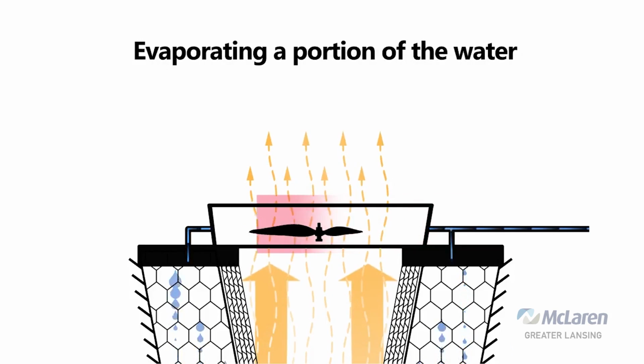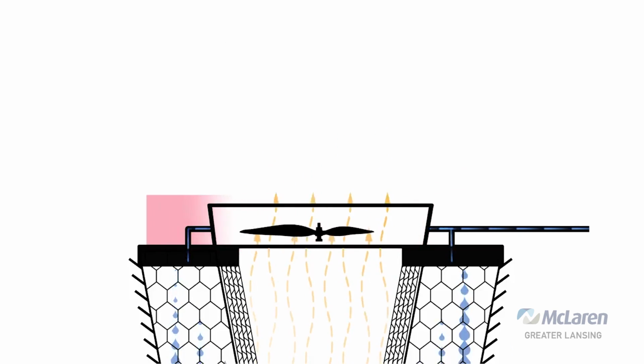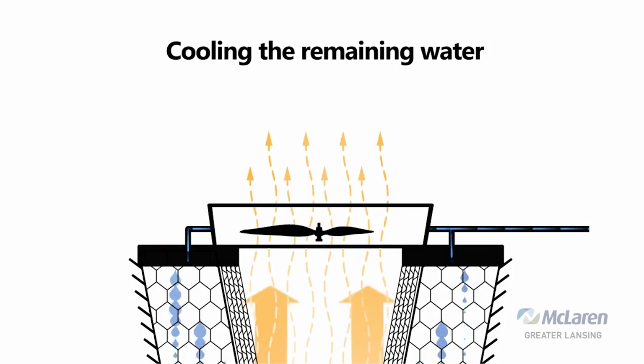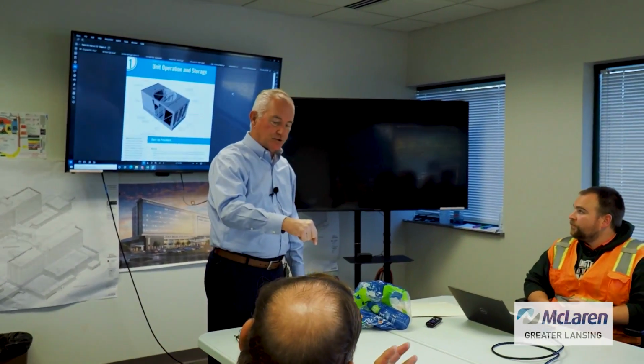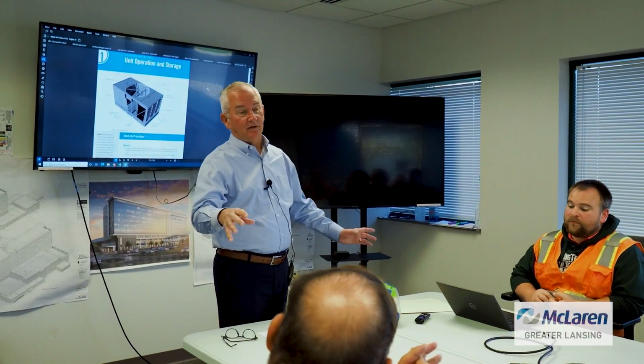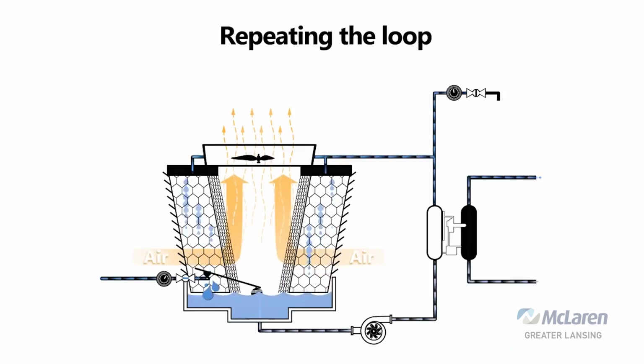Now, what you don't see in those nozzles is this little target thing. As that water comes down through the nozzle, it hits a target, splashes, hits another target, splashes. A lot of people go up there with a long flathead screwdriver and just jam the scale down into the fill material. Don't do that. You'll ruin that distribution nozzle. And then what you have is this beautiful stream of water going straight down like a laser through the fill material.